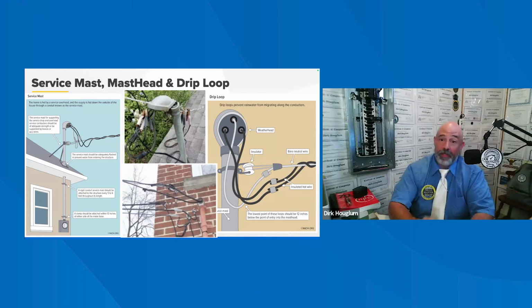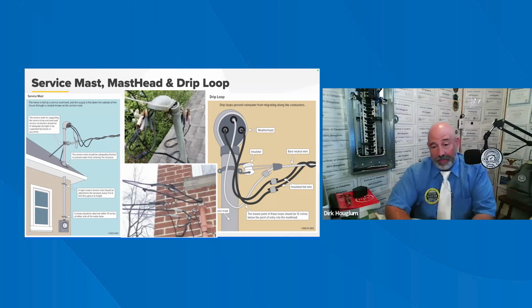First, to act as a rain cap so that moisture doesn't enter into the conduit. The second is to provide bushings to prevent individual conductors from being damaged by rubbing against metal component parts. In all electrical power situations, a bushing is an insulated device that allows the electrical conductor to pass smoothly through it and safely. The mast head should be undamaged and securely fastened to the service mast. The inspector should report any loose fittings or cracks in the mast head and its clamps. Can't tell you how many times I've seen that, especially after a storm.